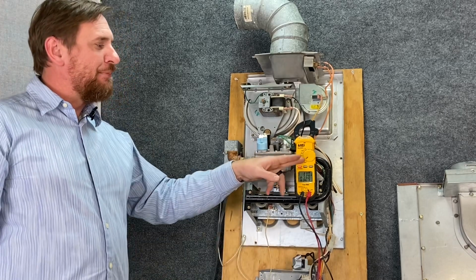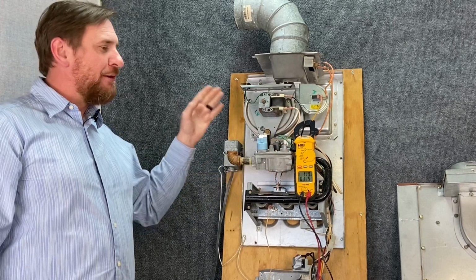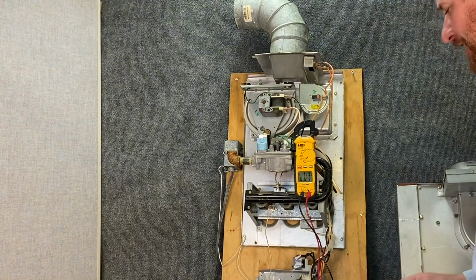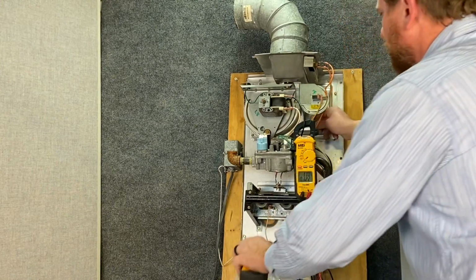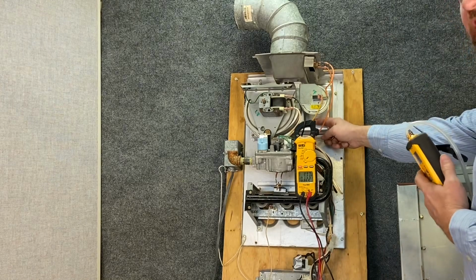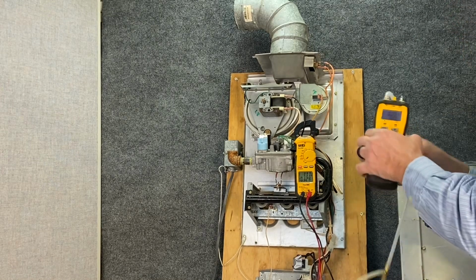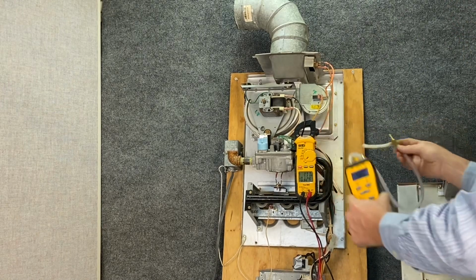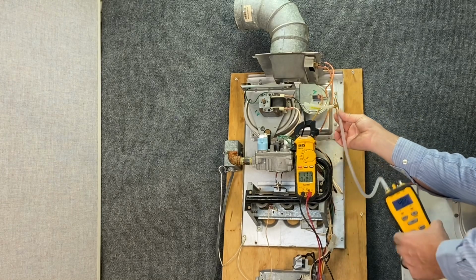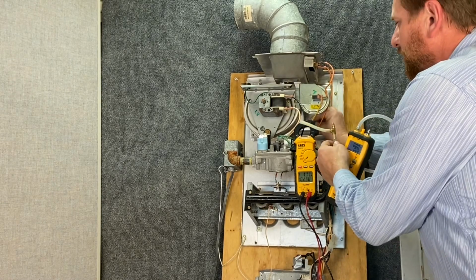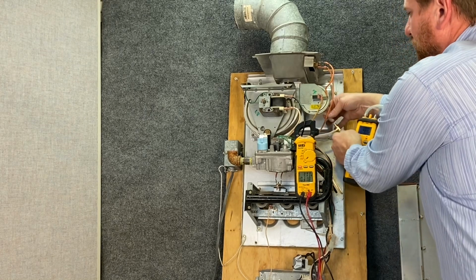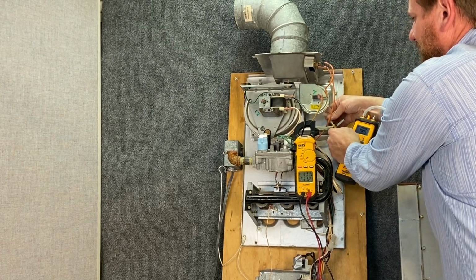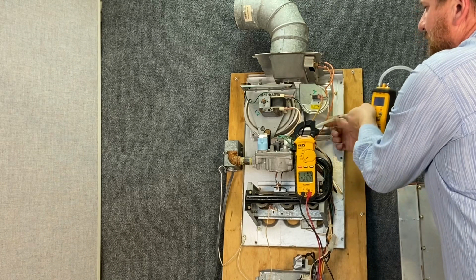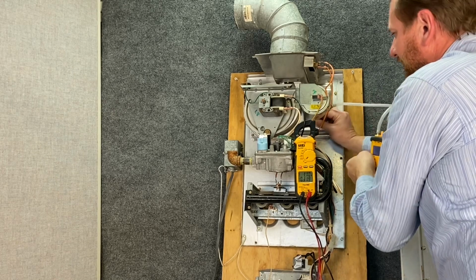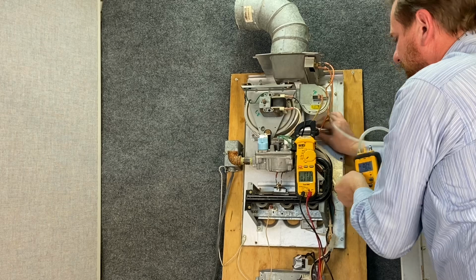So we know we have the proper voltage, we know we have the proper amperage, our bearing sounds good. Now let's check to see if it's pulling the proper vacuum. To do this, there's a little hose on the back of the collection box that goes to our pressure switch. I have my digital manometer and a T that I'm going to use. I'm going to unplug the hose to the pressure switch and plug it into the T. Then I'm going to take the hose from my T, plug it into the collection box.